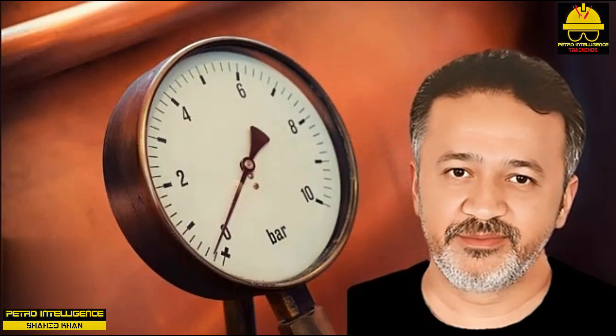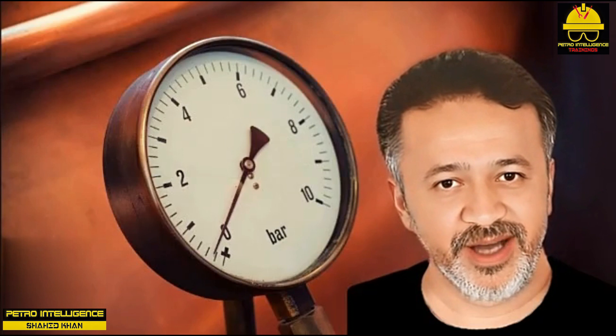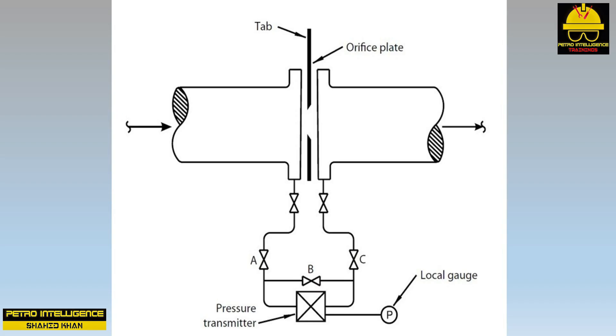Flow indication: the standard method of measuring flows in a process plant is by use of the orifice plate and orifice flanges. We rarely measure flows directly — more commonly we measure the pressure drop across an orifice plate. This pressure drop is due to the increase in kinetic energy of a fluid as it accelerates through the small hole in the orifice plate; the energy providing the increased velocity comes from the pressure of the flowing fluid.